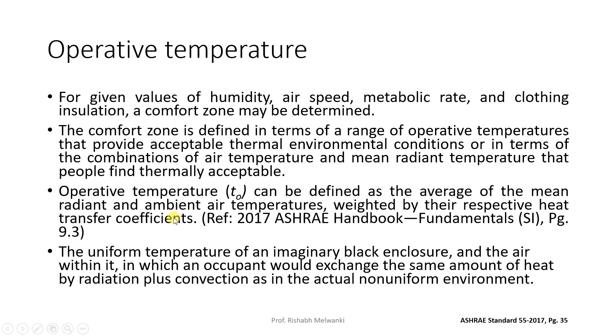Now there are two methods by which we can define the comfort zone. One is the graphical method. What do you mean by comfort zone? A thermal environment that a substantial majority, more than 80% of the occupants, find thermally acceptable. This is the definition according to ASHRAE Standard 55. This is based on two models: one is called PMV and the second is called the adaptive model. We are not going to talk about the adaptive model, we will talk about the PMV model.